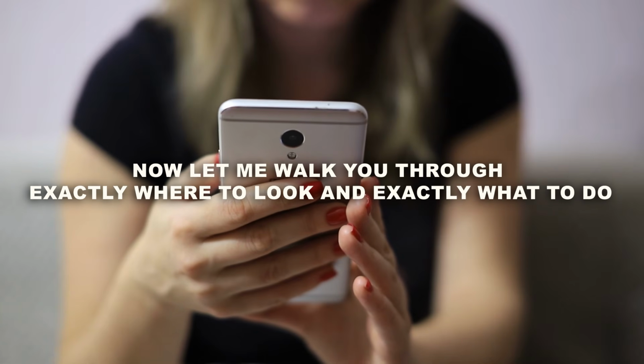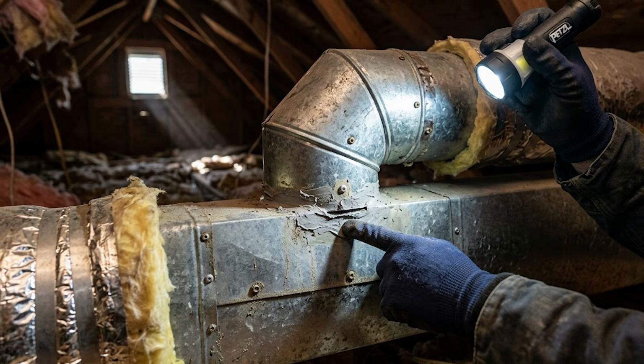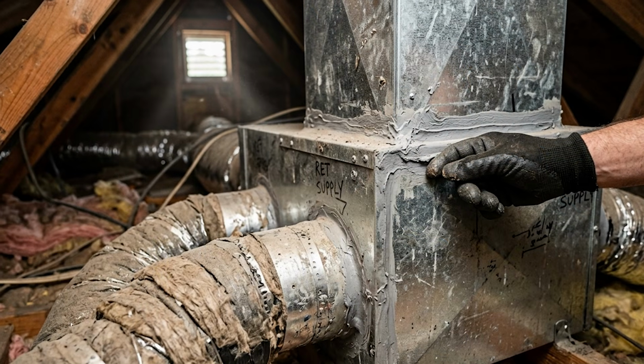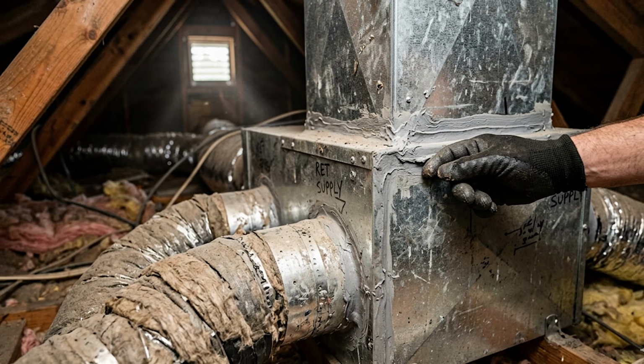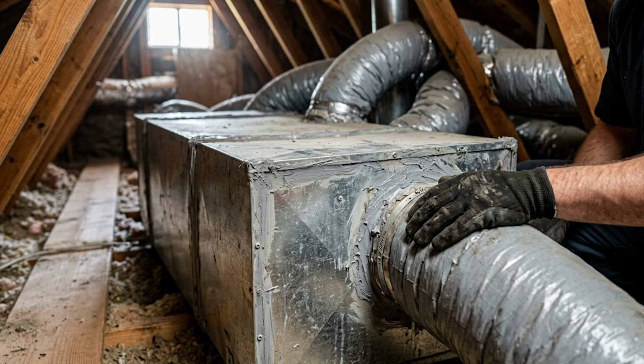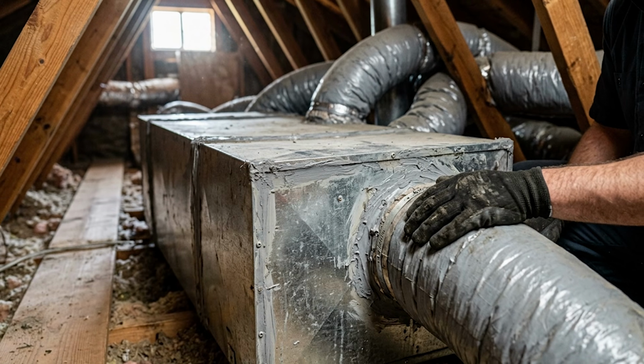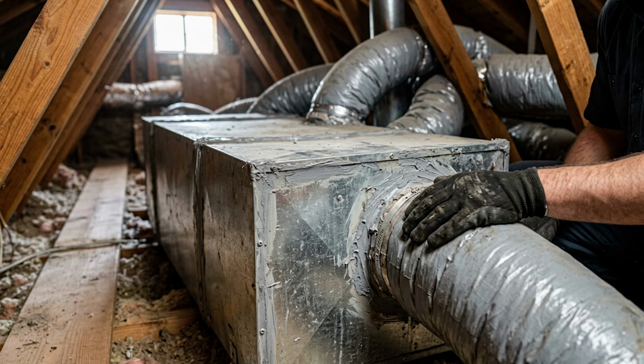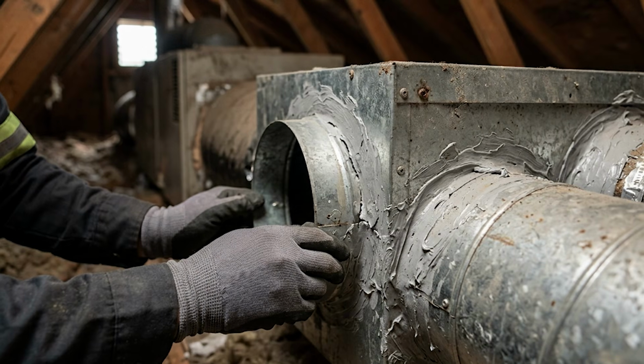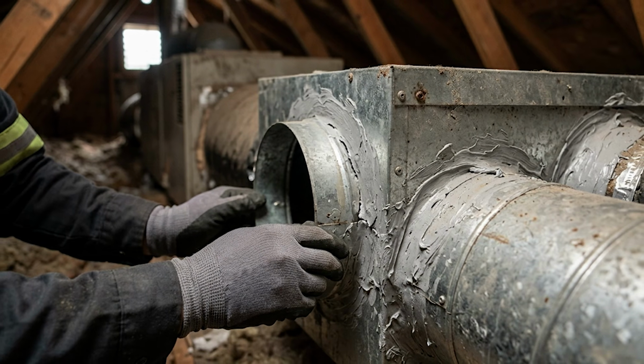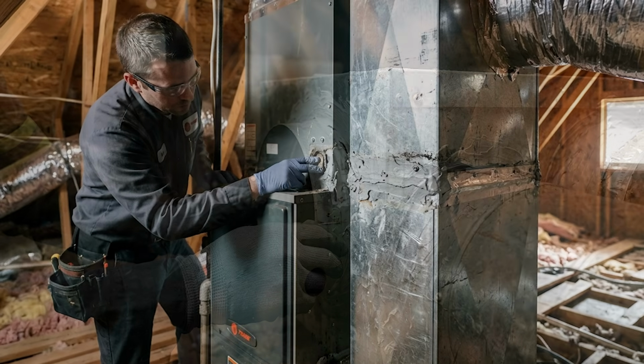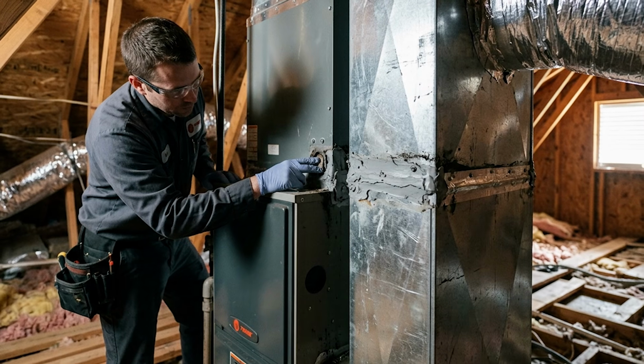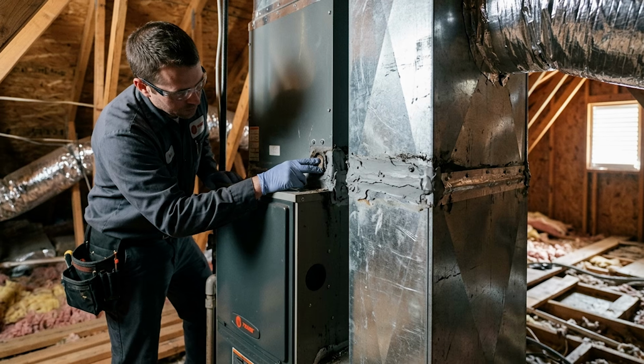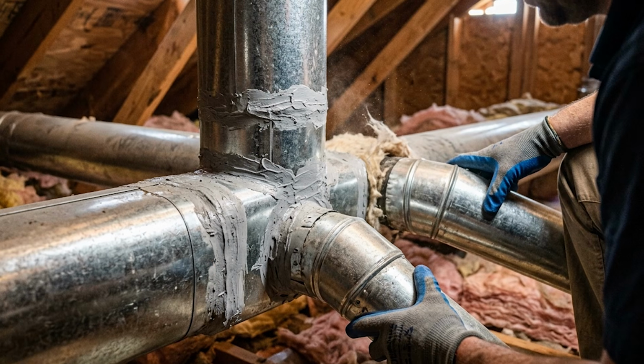Now let me walk you through exactly where to look and exactly what to do, because this is the part that most people get wrong. They go looking in the wrong places and miss the connections that matter most. The first place to check, and this is the one almost nobody starts with, is the plenum. The plenum is the large metal box that connects directly to your furnace or air handler, the point where all the ducts originate. This connection is almost always leaking. It is the single most common source of duct loss in a typical home. And because it is sitting right next to the unit itself, people walk right past it looking for the problem somewhere else. The second place is every duct joint in the attic.